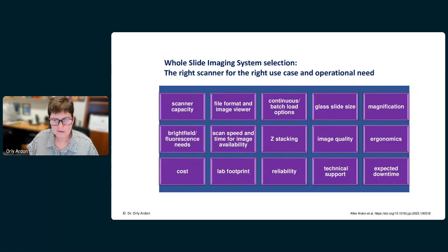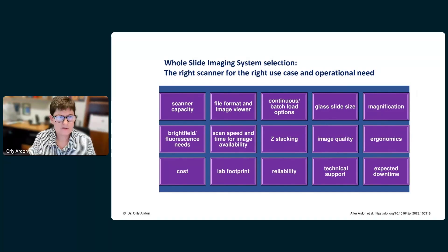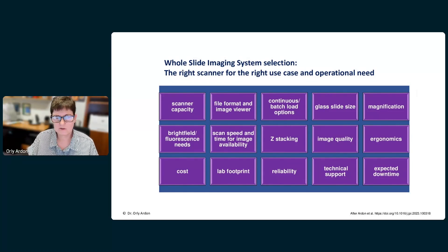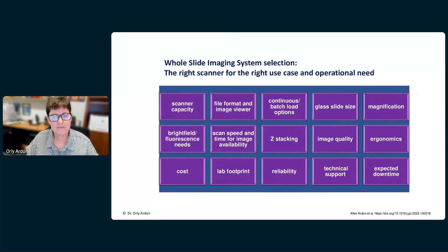The scanner is probably what most individuals are most concerned about. There are many models out there that differ in slide capacity, throughput, slide types accepted, whether they are continuous or batch load, stacking capability, scanning speed, and reliability. You also have to consider where they will fit in the lab — whether you can accommodate larger instruments or need smaller ones. Test, evaluate, talk to others, and understand the minimum requirements based on your needs and resources.